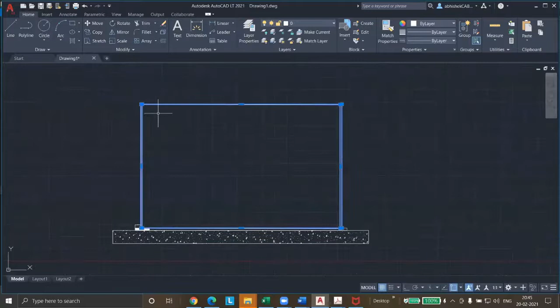Because there will be loading on this shell from the static head, it is trying to bend, and that will create a local stress in the annular plate. So the thickness has to be calculated based on the stress in the bottom shell course. The bottom shell course is affecting the design of your annular plate. So if the annular plate thickness changes, we just have to change the annular plate thickness, and the bottom plate will remain as it is. It will save you lots of cost.